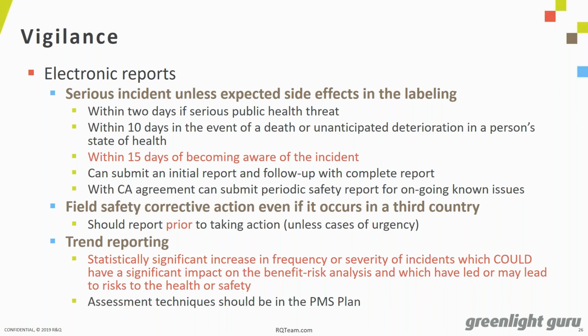And then you need to notify them even if this field safety corrective action is taking place in a third-party country, so in another country outside the union or something like that, you still need to notify them of those actions. And then again, the MDR added some new requirements to the trending, that the trends that you're assessing on the devices or on the complaint history or whatever your post-market data is, that you're assessing the frequency of that, and it needs to be a statistically significant change, as well as you need to be evaluating changes in potential severity. All need to be considered for trends, not just the frequency of those trends or complaints or issues that you're seeing in the field.